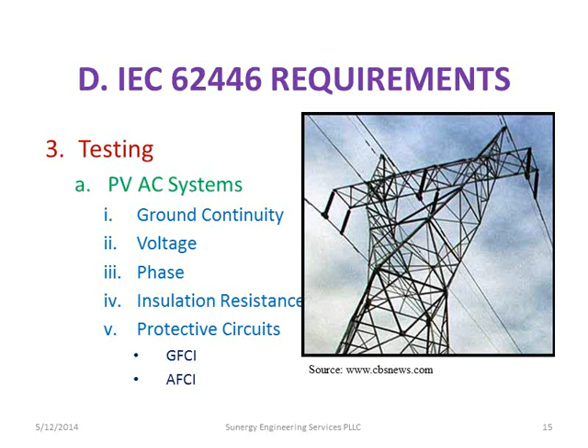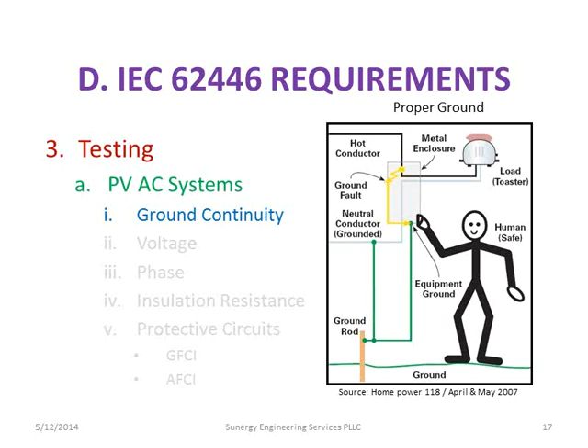So the IEC 62446 requires testing of the PV AC systems. So that's on the grid side of the inverter. And the first one is ground continuity. And that's a pretty important one, because if there's a short, that's what's protecting me from becoming the grounding rod. So, and especially when you're doing these types of tests, because these tests are done on live circuits. You can't do these tests without having the system actually running. So you want to make sure that the ground continuity is good. When it's good, we're happy.